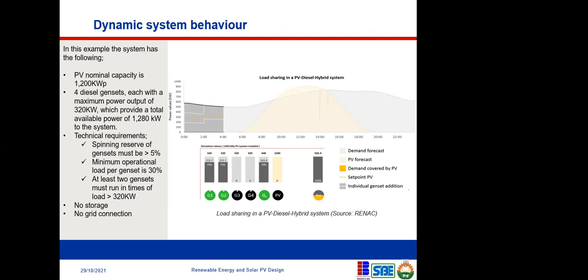And the reason is this. I talked about dispatchable and non-dispatchable generators. Solar system is non-dispatchable, meaning that you cannot call it on demand, it can disappoint. Let me not say fail, so that people will not think solar systems can fail at some point. No, that is not it. The solar system is not 100% reliable. That is the right word. It's not 100% reliable unless you have a massive amount of battery storage. But if you want to optimize cost, then you don't put in a large amount of battery storage because it will make the whole project financially unviable.